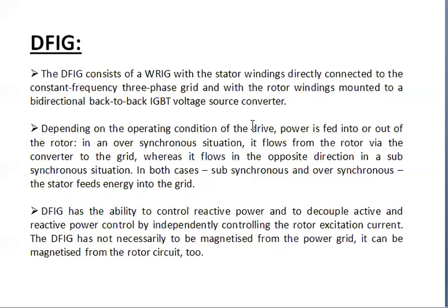And depending on the operating condition of the drive, power is fed into or out of the rotor. In an oversynchronous situation, it flows from the rotor via the converter to the grid, whereas it flows in the opposite direction in a subsynchronous situation. In both cases, subsynchronous and oversynchronous, the stator feeds energy into the grid. So the DFIG, that means doubly fed induction generator, has several advantages.